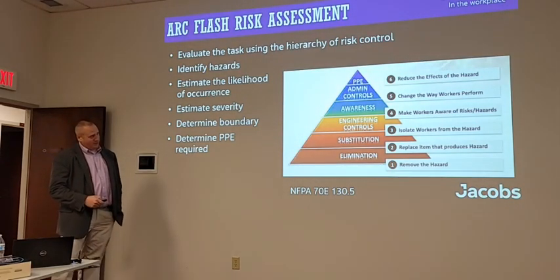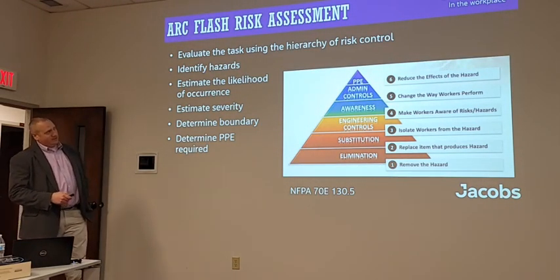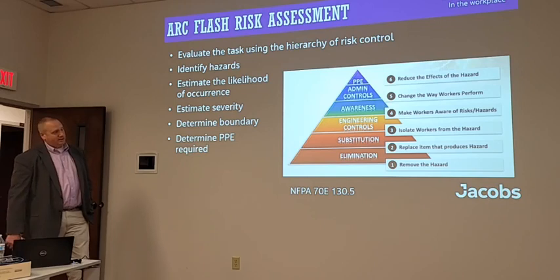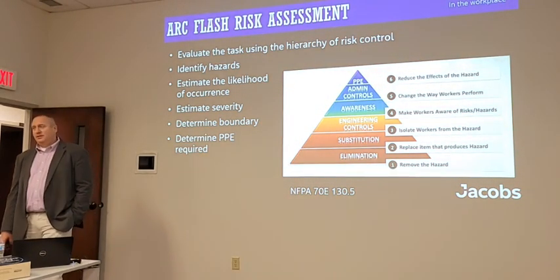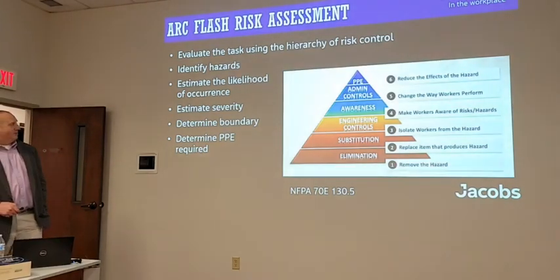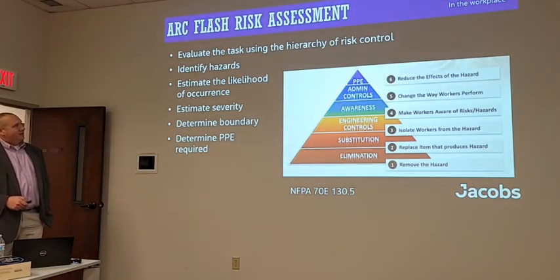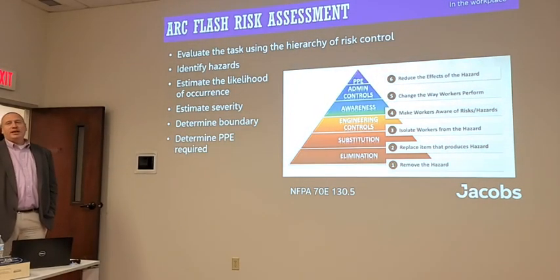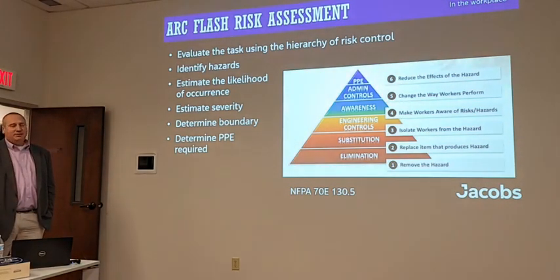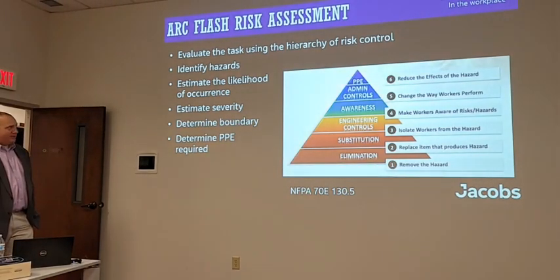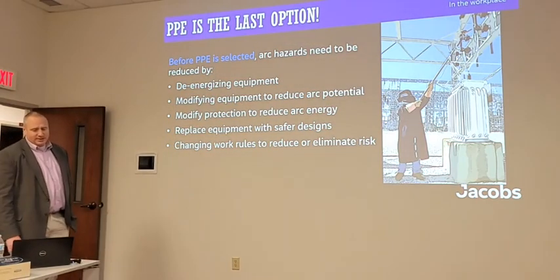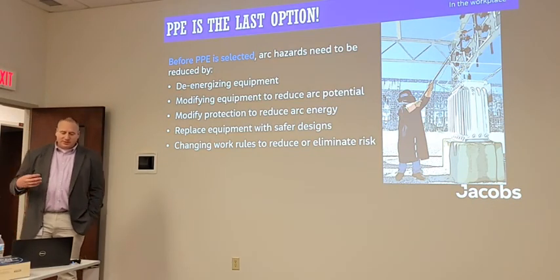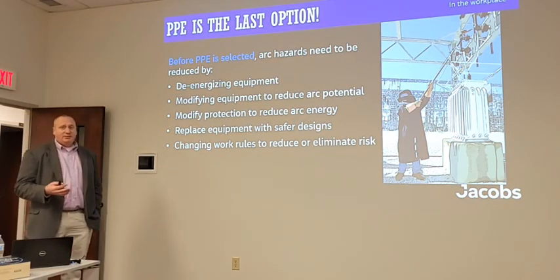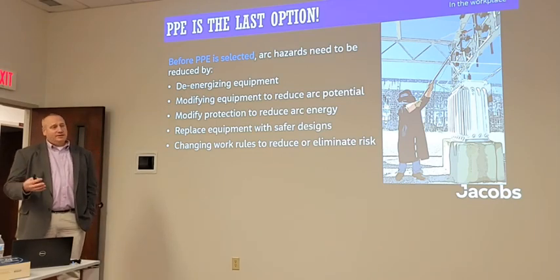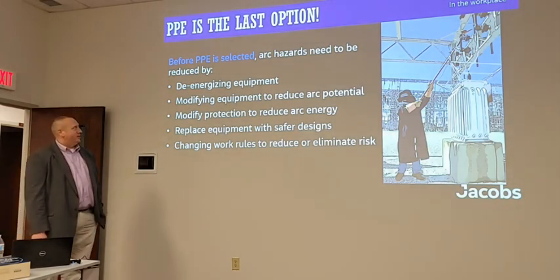And then substitution and engineering controls, these are all down to the effectiveness to where your last line of defense is PPE. So just because there's PPE available doesn't mean we go throw our stuff on and go do the work. We always want to go through this analysis to figure out, is there another way to do it to where we stay outside the hazard, we're not exposed to the hazard to where we don't have to have the PPE on. Because the reality is PPE is our last option. We would prefer to reduce the arc flash hazard by de-energizing the equipment, but keep in mind, de-energizing the equipment, you're starting, stopping current flow, so that could also have an arc flash hazard. So you need to evaluate that as well.